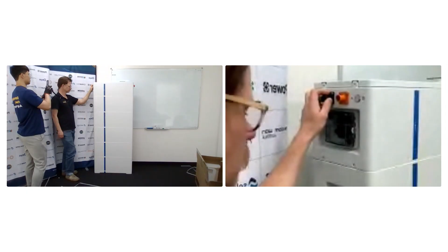The thing that I like about this concept, and I've tested this with the inverter already, is that the batteries and the inverter, even though they're part of this integrated system, can operate independently of each other. So if in the future something happens to the batteries and they don't work anymore, and you can't get any more of them because Deye have stopped making them, you would still be able to use the inverter, say with some Discover or Pylontech batteries, because the inverter is exactly the same as the normal Deye inverter that mounts on the wall. It's exactly the same.